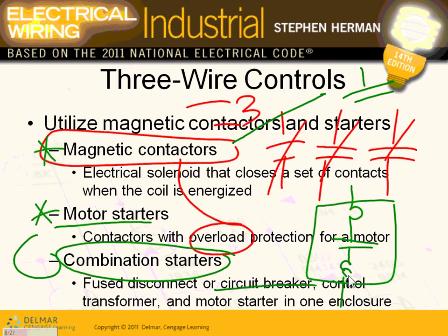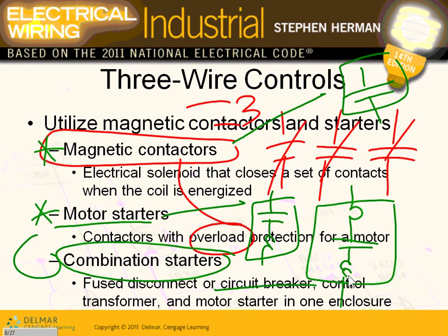This one is only the contactor. This one is the contactor and the overload — motor starter. This one is all three together — combination. MCCs: when we design an MCC and we talk about pockets — like when we went to Boston Scientific — the pockets actually include an overcurrent protection device (fuse or circuit breaker), a contactor, and an overload.